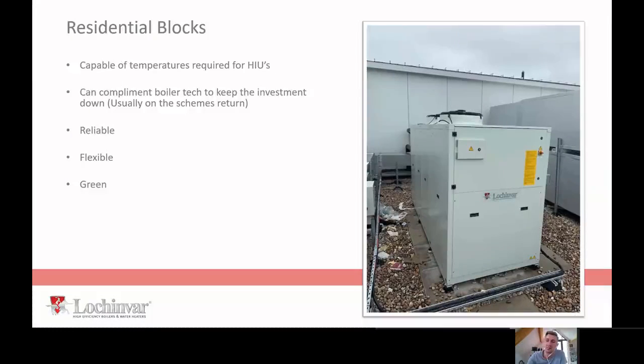Resi blocks. So when you've got heat interface units demanding 70 degrees centigrade and a 40 return, that water source heat pump arrangement we looked at earlier allows us to flow at these inflated temperatures to service full electric only residences, which is fantastic. And yeah, there are an endless number of projects in this sort of format now, high-end resi.